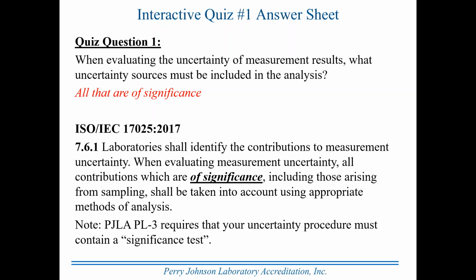It's one of those things where professionals working in the metrology industry should have an awareness of what is significant and what isn't. But for those of you who are interested, I'm going to give you a rule of thumb that I use myself when I have my own laboratory and in consultation with other labs. If one or more contributors to the overall uncertainty of a result, taken as individuals or taken as a group of small contributors, contribute no more than 1% of the total, then they can be considered as insignificant. So again, an individual contributor taken by itself or several contributors taken together do not contribute more than 1% to the total. That individual or that group of individuals can be considered as insignificant. What that means then is everything left has to be considered as significant and included in the analysis.